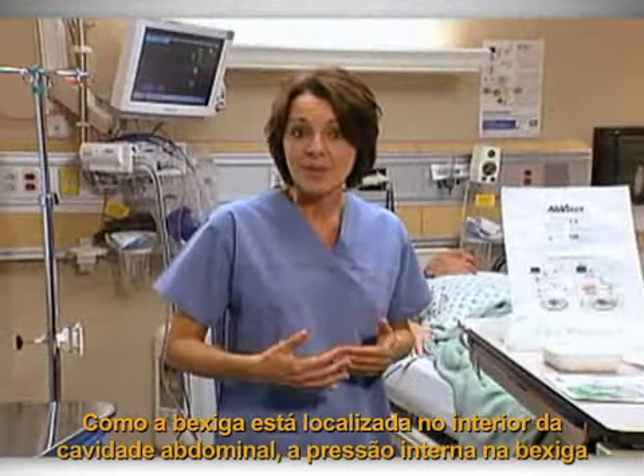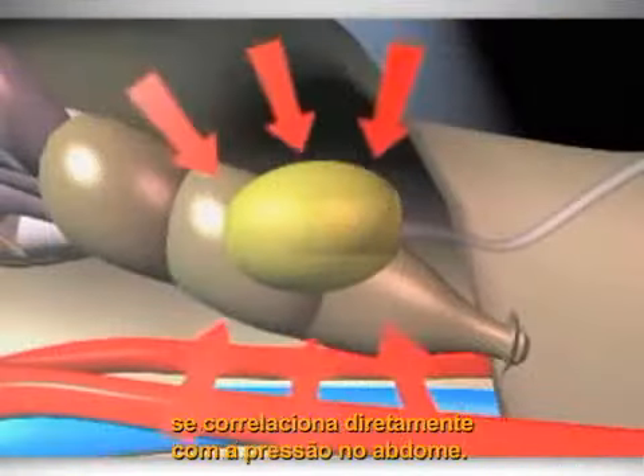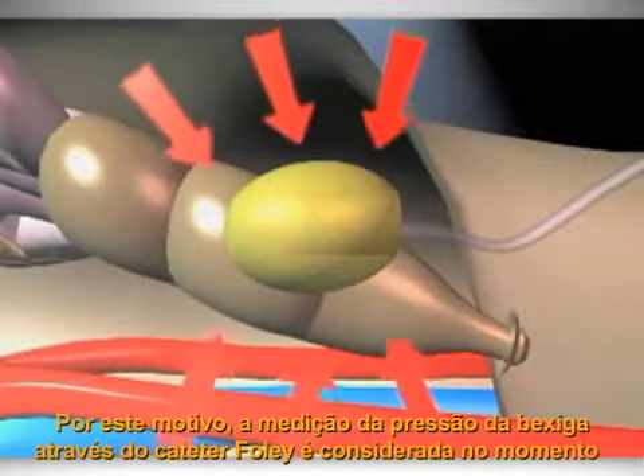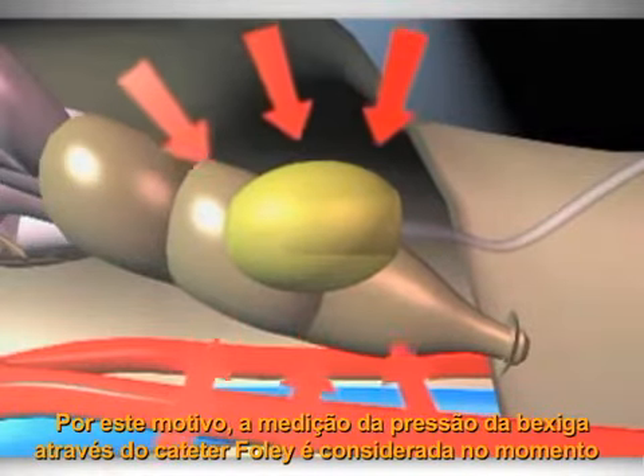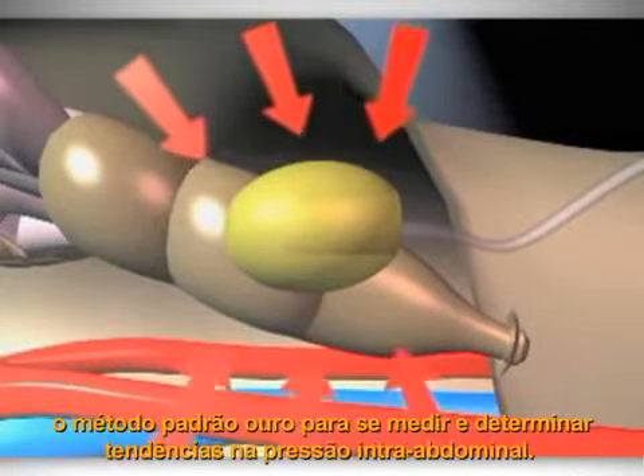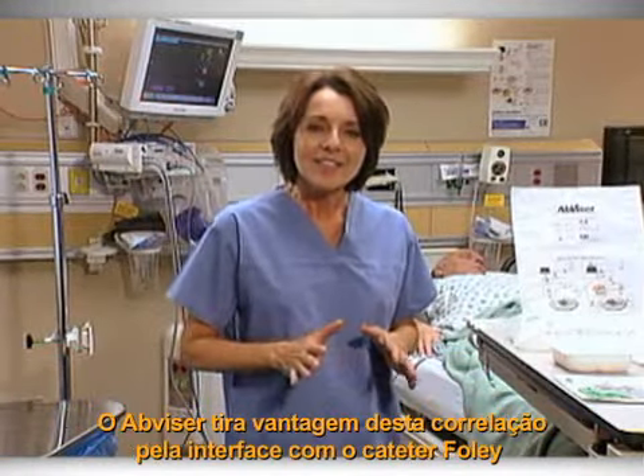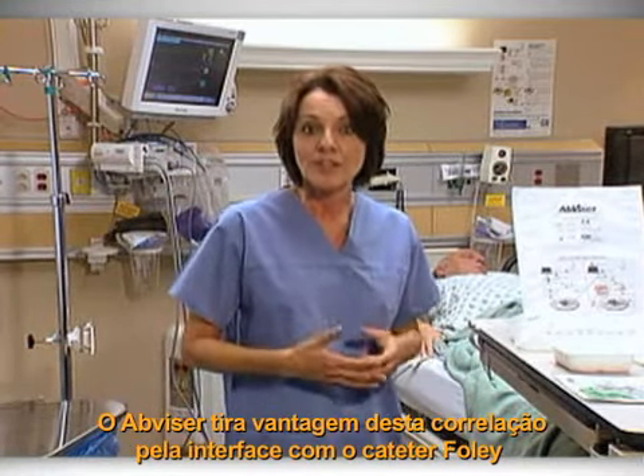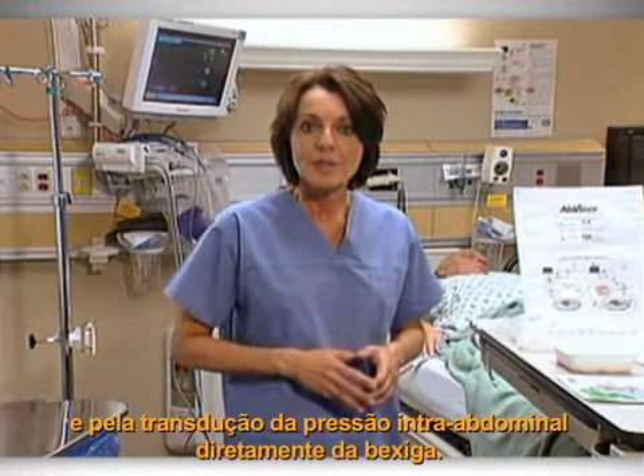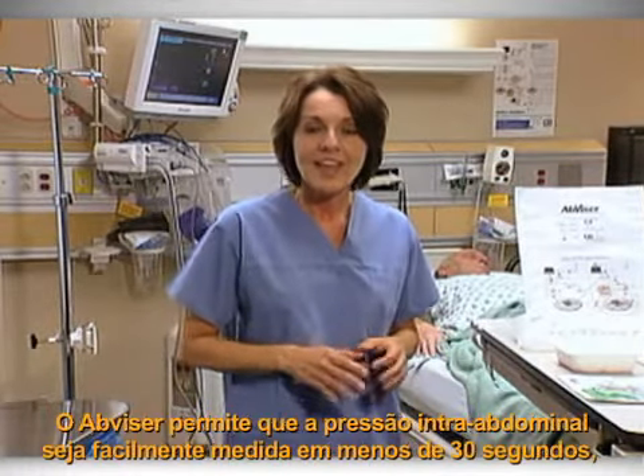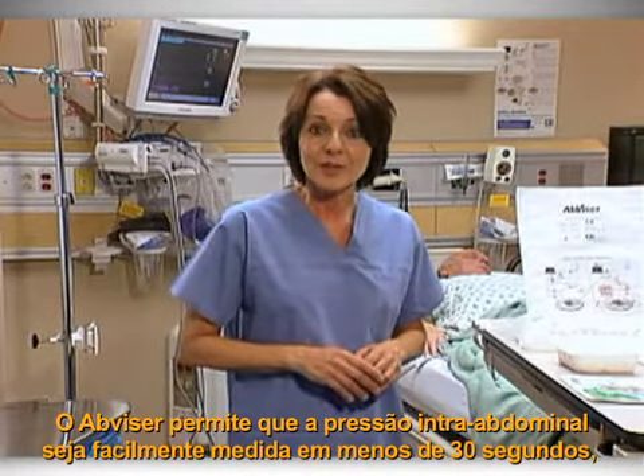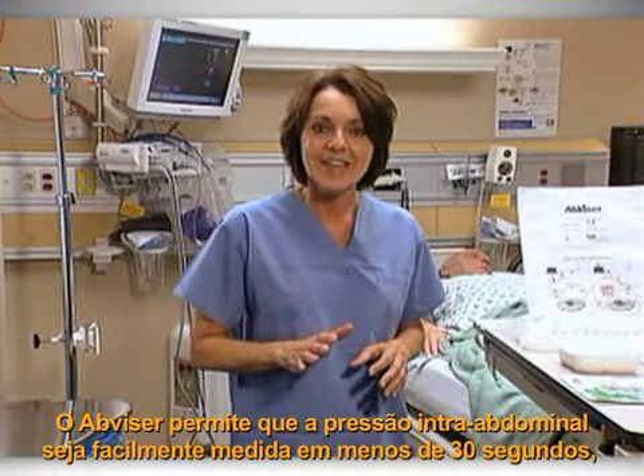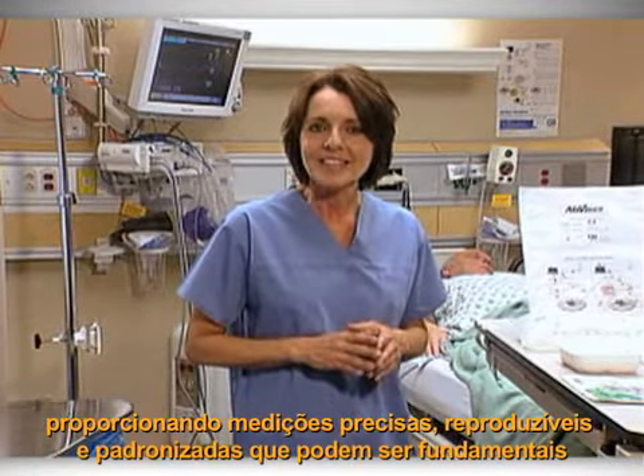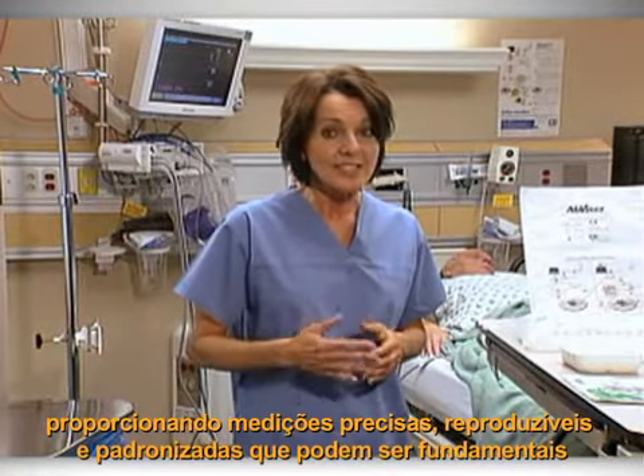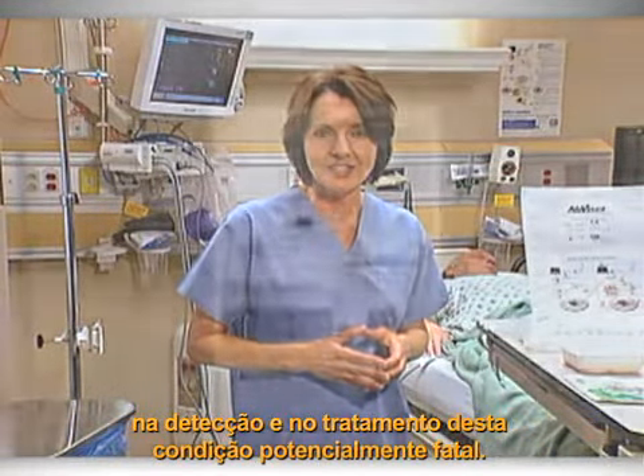Because the bladder is contained within the abdominal cavity, pressure within the bladder directly correlates with pressure in the abdomen. For this reason, bladder pressure measurement through the Foley catheter is now considered the gold standard method for measuring and trending intra-abdominal pressure. The Abviser takes advantage of this correlation by interfacing with the Foley catheter and transducing intra-abdominal pressure directly from the bladder. The Abviser allows you to easily measure intra-abdominal pressure in less than 30 seconds, providing accurate, reproducible, and standardized measurements that can be critical in detecting and treating this life-threatening condition.